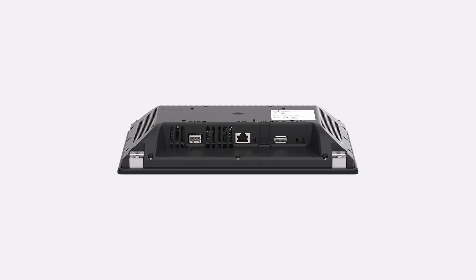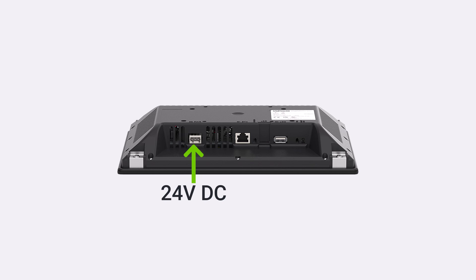The WebPanel 400 can be powered either via power over Ethernet or through a 24V DC power source. Due to the capacitive touch, a grounding connection is also required from a system perspective.